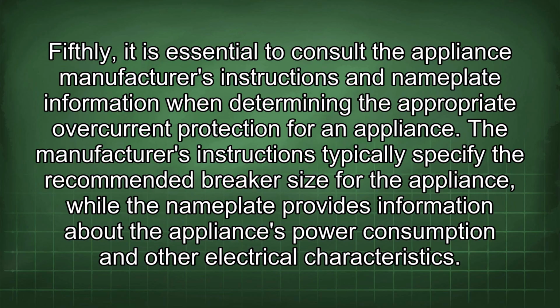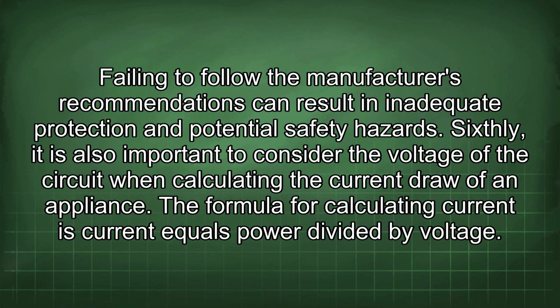Fifthly, it is essential to consult the appliance manufacturer's instructions and nameplate information when determining the appropriate overcurrent protection for an appliance. The manufacturer's instructions typically specify the recommended breaker size for the appliance, while the nameplate provides information about the appliance's power consumption and other electrical characteristics. Failing to follow the manufacturer's recommendations can result in inadequate protection and potential safety hazards. Sixthly, it is also important to consider the voltage of the circuit when calculating the current draw of an appliance.